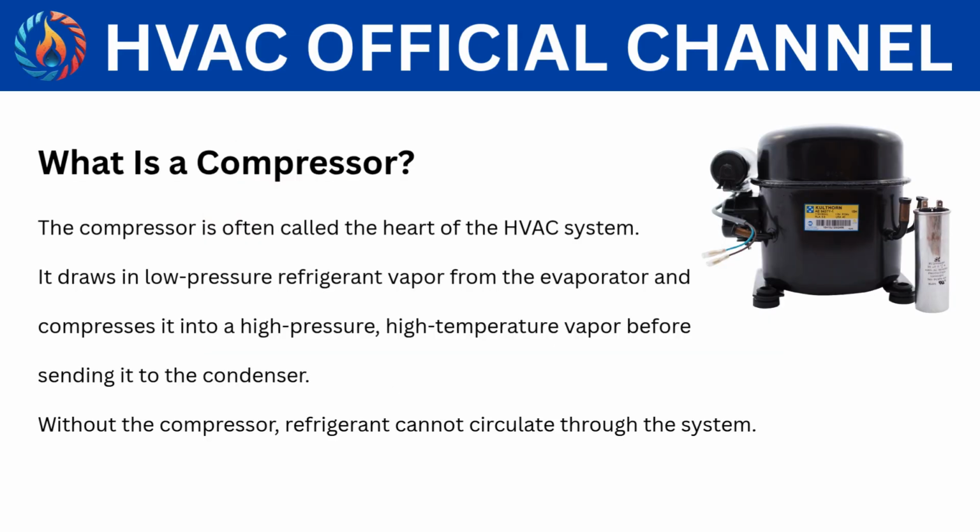What is a compressor? The compressor is often called the heart of the HVAC system. It draws in low-pressure refrigerant vapor from the evaporator and compresses it into a high-pressure, high-temperature vapor before sending it to the condenser. Without the compressor, refrigerant cannot circulate through the system.